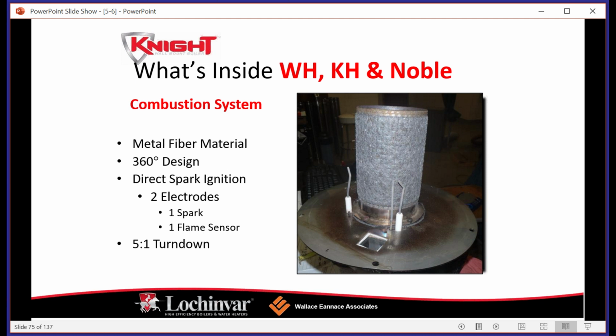Okay, so once the air-fuel mixture is pushed through that fan, it goes into the burner, okay? So now this is the Knight wall hung, the Knight floor, the Noble. This is a metallic fiber burner, okay? On old school non-condensing boilers, you would basically have a flame like you would see on a tea kettle or a water heater or something like that. What we're doing with this is using a metallic fiber material. And again, this is the same kind of material we're going to see across all of the condensing equipment.